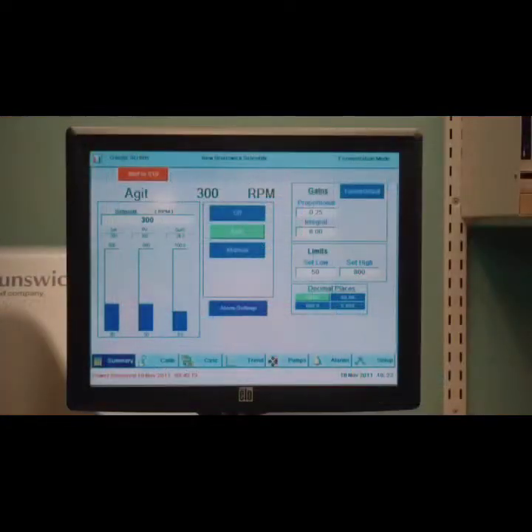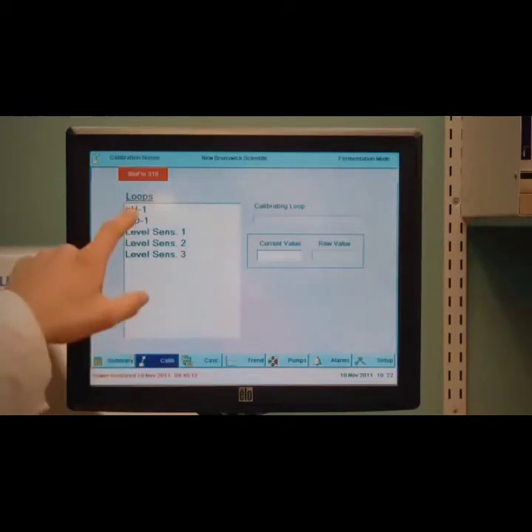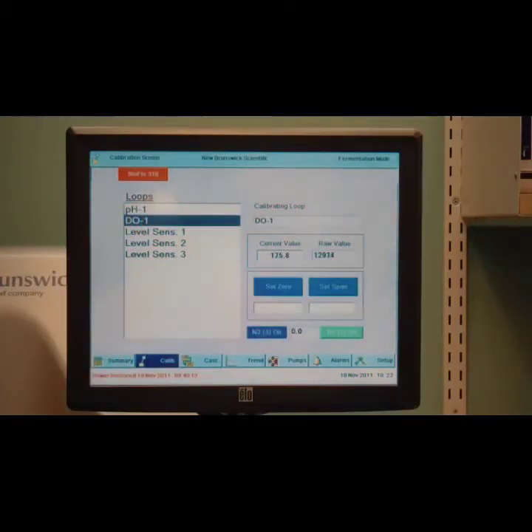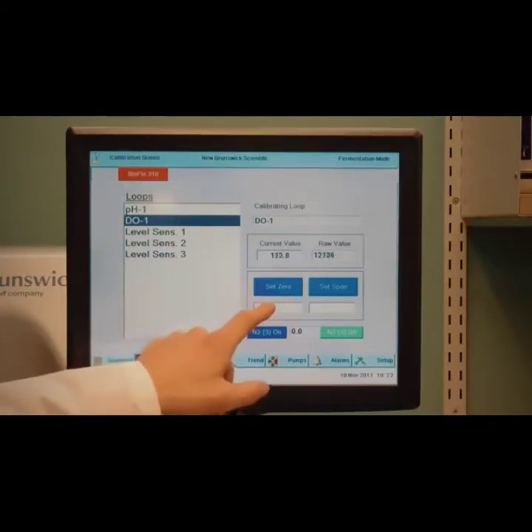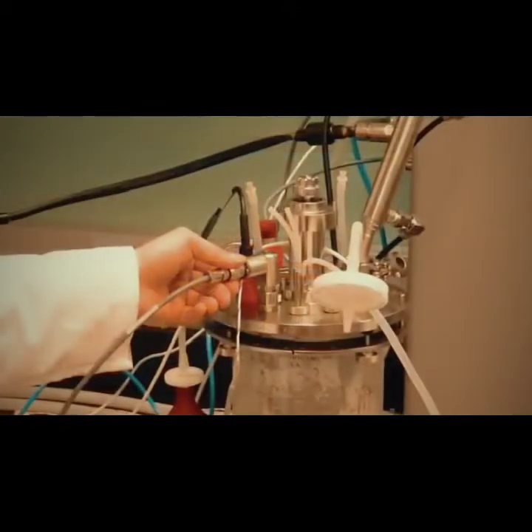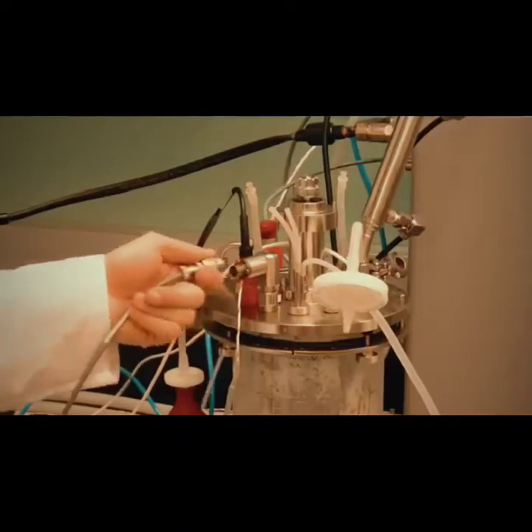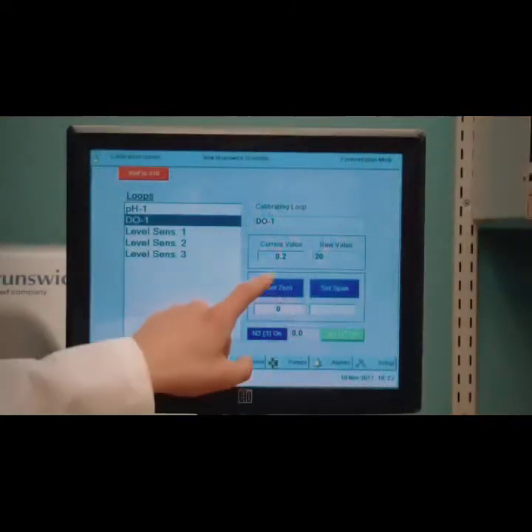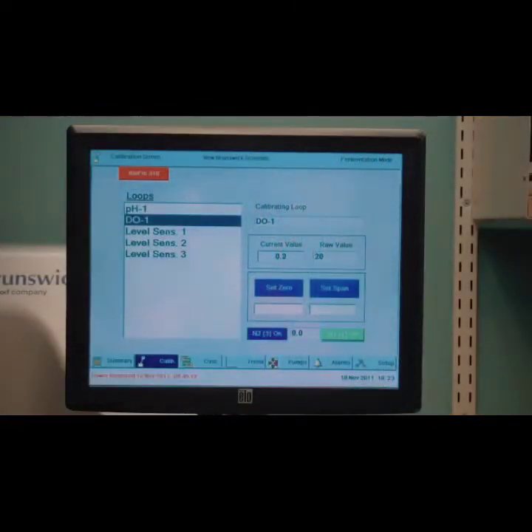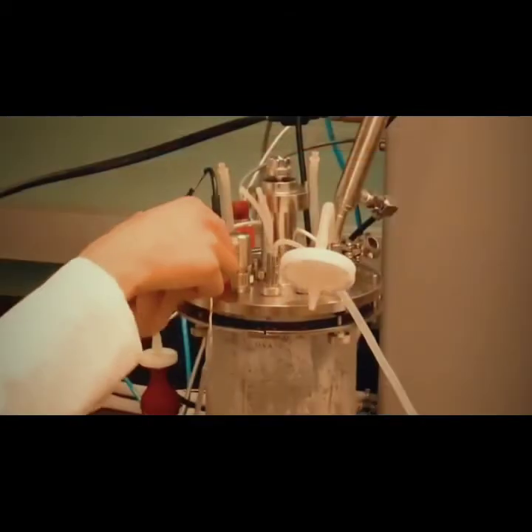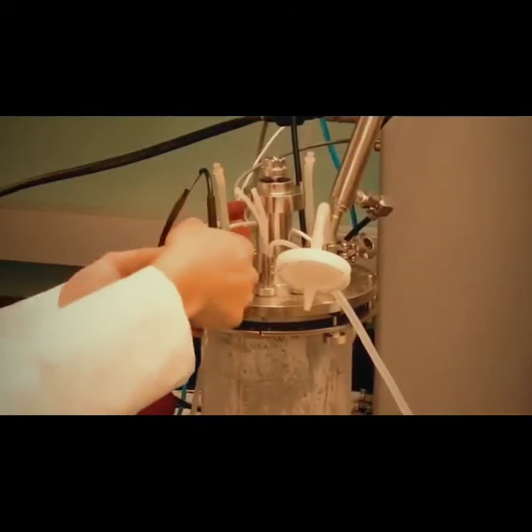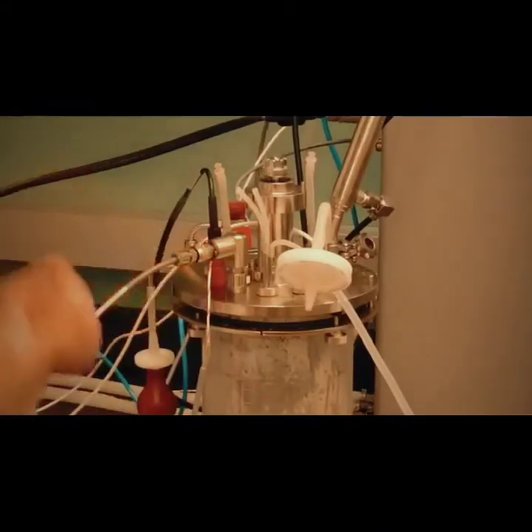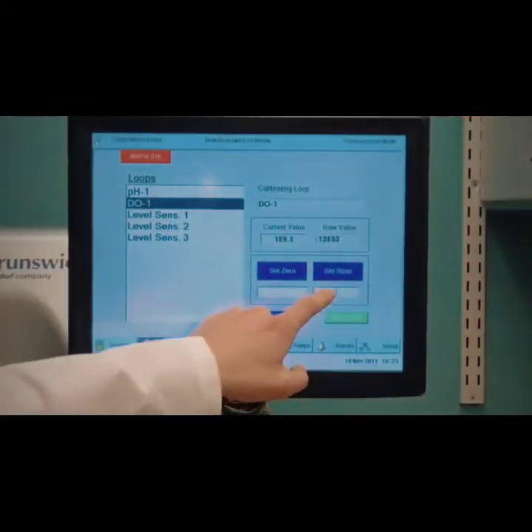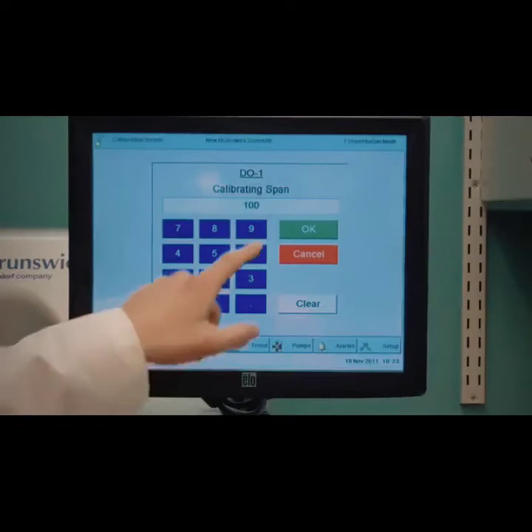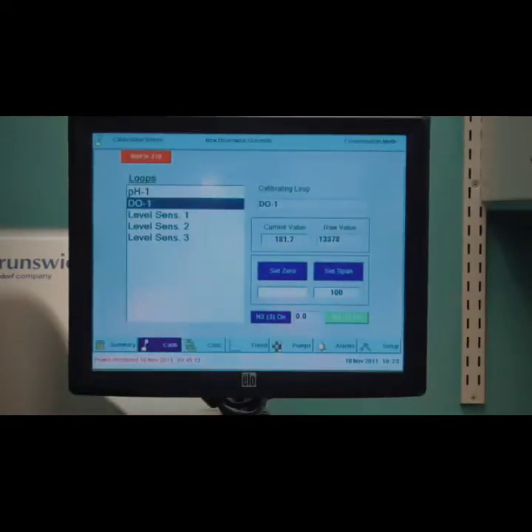On the PCU, select calibrate, then dissolved oxygen probe. Type 0 into the box below the set 0, but do not press set 0 yet. Momentarily disconnect the cable from the dissolved oxygen probe. When the raw input stops decreasing, press set 0. Reconnect the cable to the dissolved oxygen probe. Type 100 into the box below the set span button. When the raw input stops increasing, press the set span button.